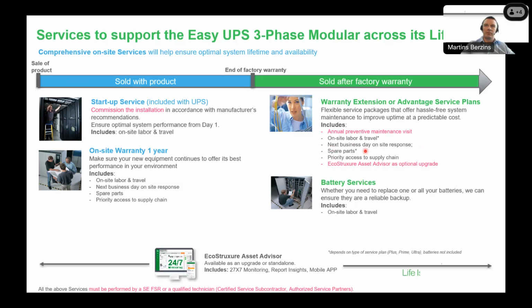Regarding the spare parts, we have several service plans. We have a service plan that includes spare parts, and then you basically have full insurance of the UPS in case of a break, or we have service plans where spare parts are not included. In case of a failure, the field service engineer will issue an offer, saying this spare part costs this much, are you okay to purchase it and replace it? And of course, all the UPSs under a service contract have priority access to the supply chain, or priority access to the spare parts. Locally we keep spare parts for the UPSs, and they are prioritized for customers with a service plan, so we can fix or replace any failed parts as soon as possible.